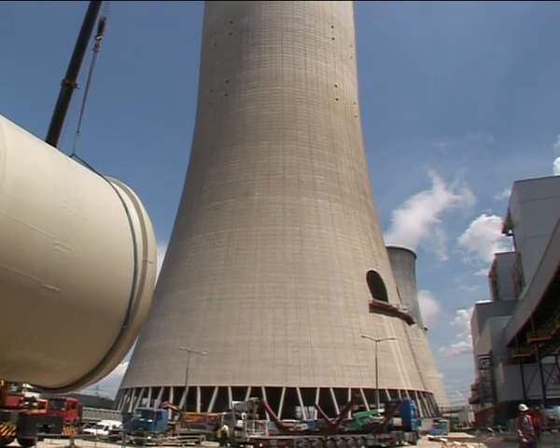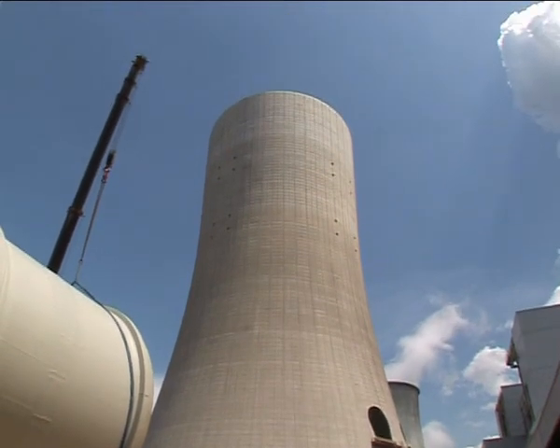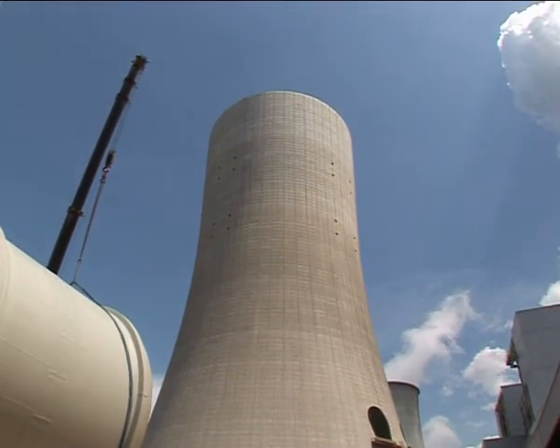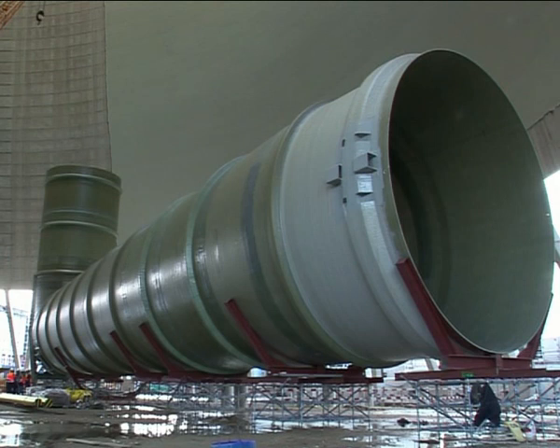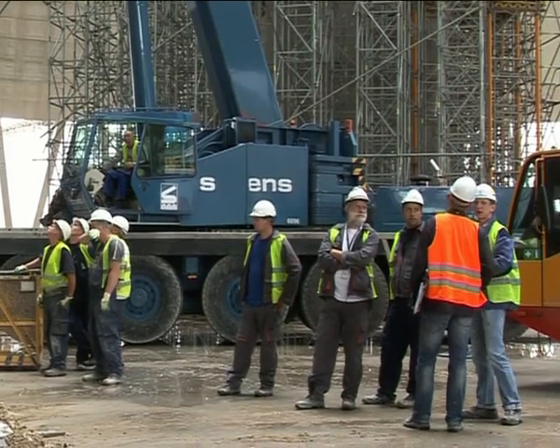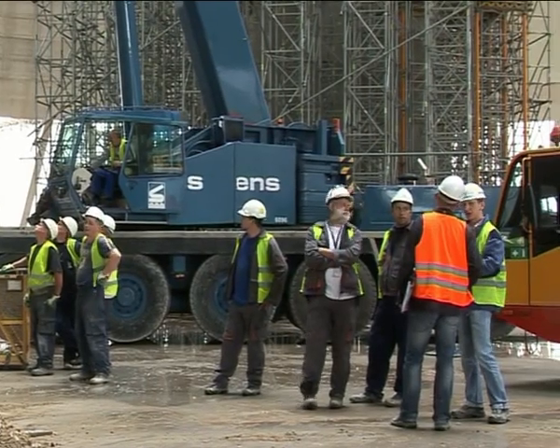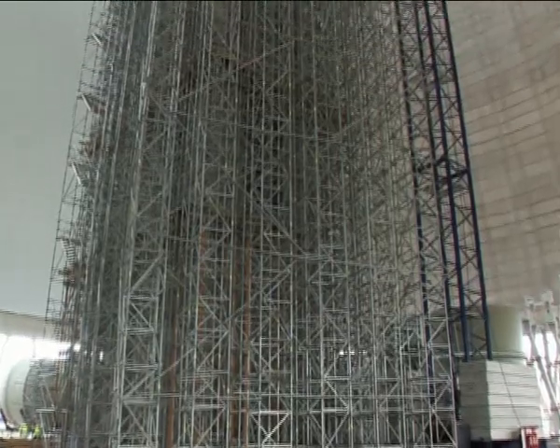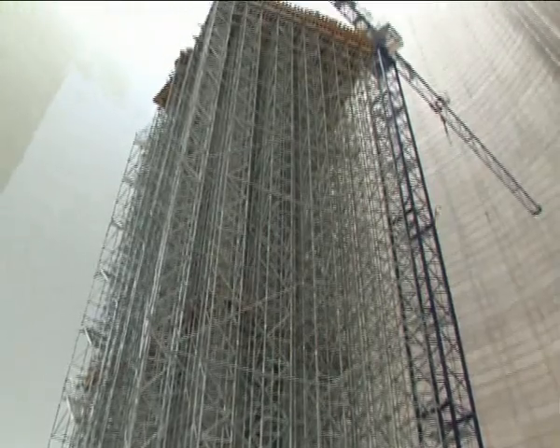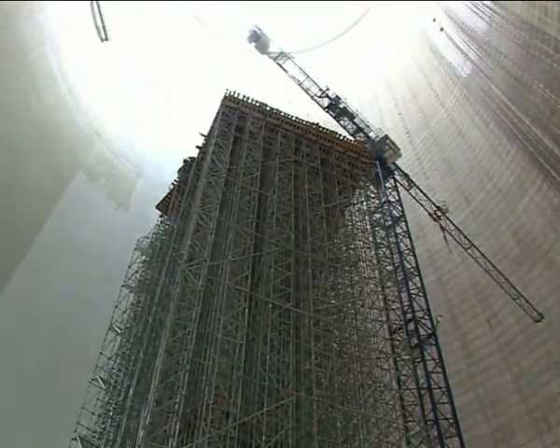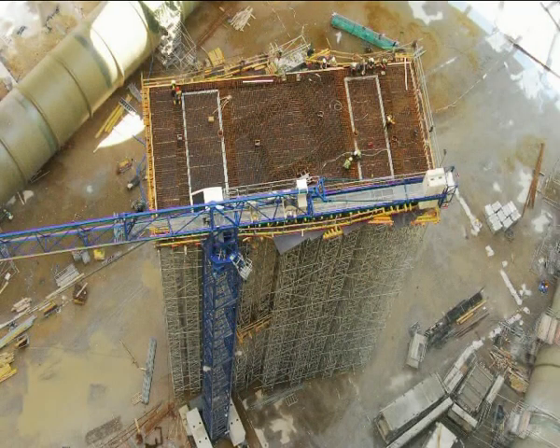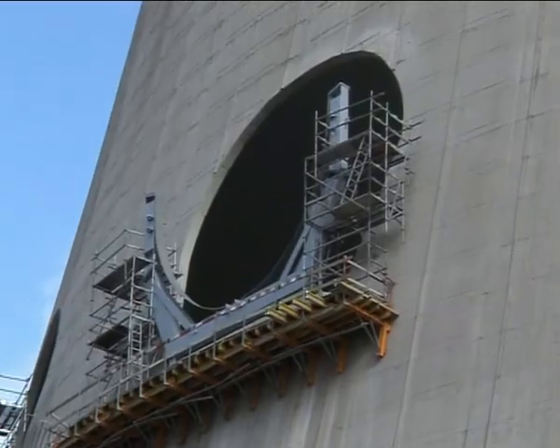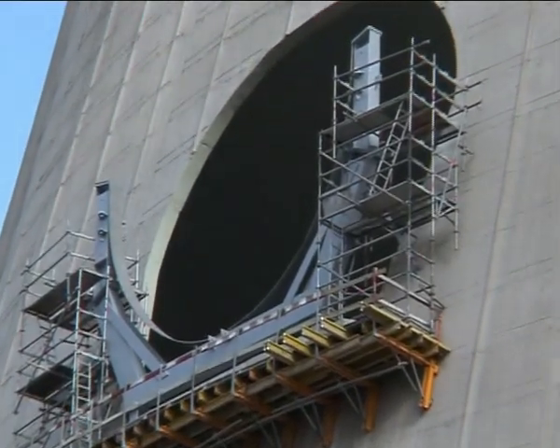As already mentioned, the cooling tower also functions to exhaust combustion gases. The exhaust pipes cannot have any intermediate points of support inside the structure. Therefore, the only internal support for the pipes is a centrally placed structure with a reinforced concrete slab located at a height of 34 metres. The second point of support is the shell.